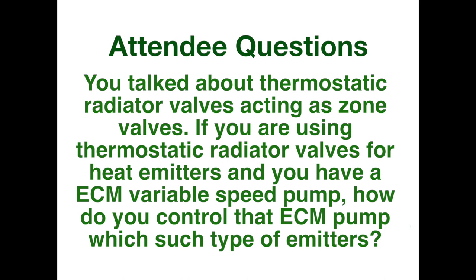Yeah, there's a lot of times where, say you're running a boiler that's operating with a set point controller that's wired into the buffer tank. So the boiler a lot of times will maintain the buffer tank based on an outdoor reset curve. From there, on the other side of that buffer tank, you put in one of your variable speed, differential pressure based circulators, and then you just operate the boiler off of a central thermostat. In a lot of cases, you take that central thermostat and put it about 1 or 2 degrees above your desired temperature throughout the house. That operates the boiler to turn on to heat the buffer tank. And then the variable speed circulator on the other side does its own thing.